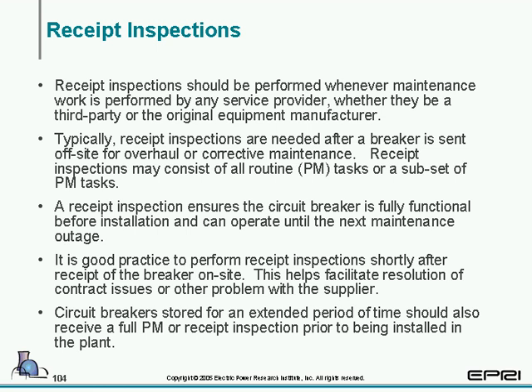Receipt inspection should be performed whenever maintenance work is performed by any service provider, whether a third party or the original equipment manufacturer. Receipt inspections are needed after a breaker is sent offsite for overhaul or corrective maintenance. It may consist of a routine preventative maintenance task or a subset of these tasks. This type of inspection ensures the breaker is fully functional before installation and can operate until the next maintenance outage.